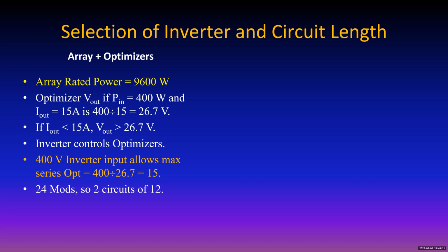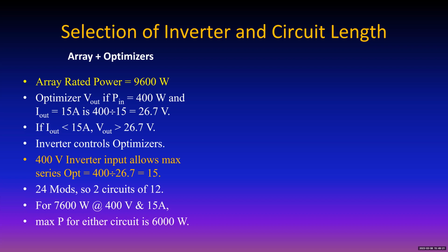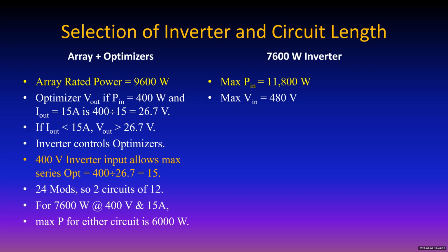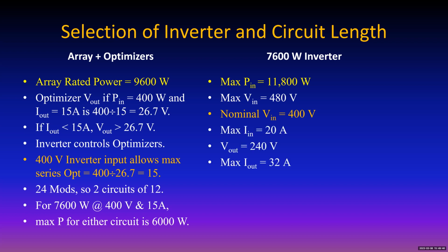So if you have two circuits of 12 this time, then if you have a 7,600 watt inverter, 400 volts, 15 amps, the maximum power for either of those two circuits would be 6,000 watts. Okay, here's the 7,600 watt inverter. I use that because that's a very common one, but they come in a lot of other sizes, 11,400 being another common size. And again, we're matching up the devices so that they're happy working together. Okay.